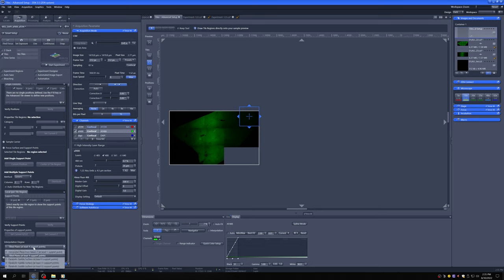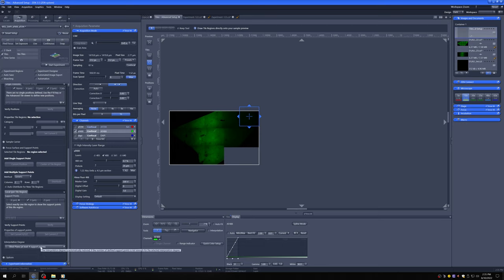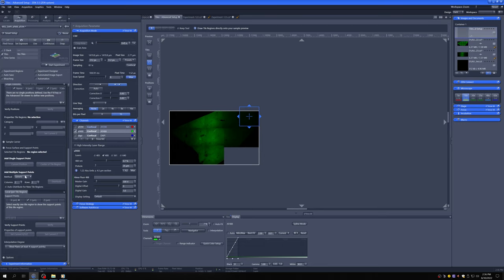And then for the interpolation degree, you use a tilted plane. This assumes that your slide is tilted in a plane, which is a good assumption for a slide that's tilted for the reason I mentioned, which is a coverslip that extends all the way towards the end. Once you create a tiling region, then you can add to it these support points, which will allow you to tell it what the proper focus is at each position and compensate accordingly.